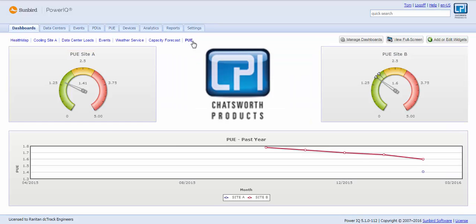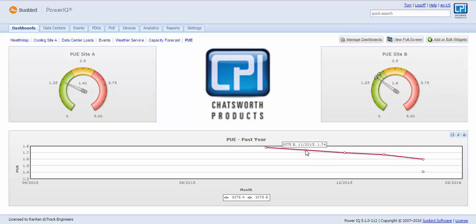We make it easy to track PUE at any level by site, trend over time. This can be fully automated to have the highest accuracy PUE where you're collecting load from facility objects as well as IT objects updated daily. Or, if your metering infrastructure is not fully mature and you have the need to enter manual readings for part of your total facility load or part of your IT load, we provide that type of flexibility.